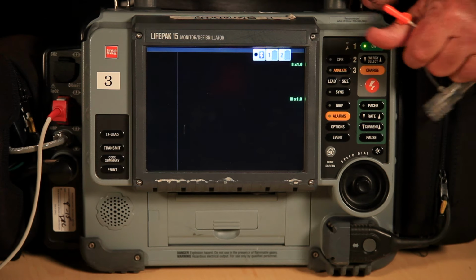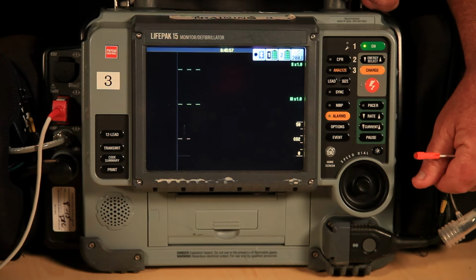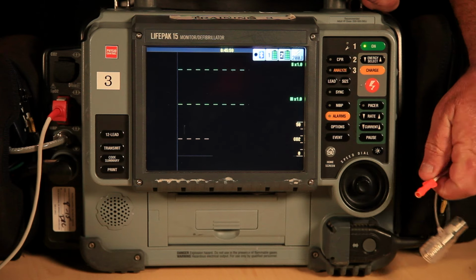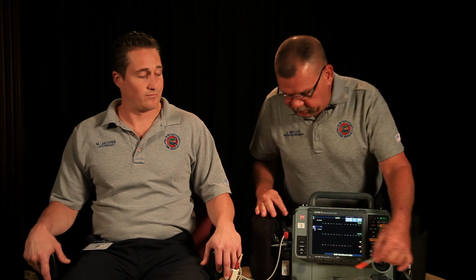When we power up our LifePak 15, it runs through its self-test, and our machine factory defaults at lead 2, lead 3, and capnography.